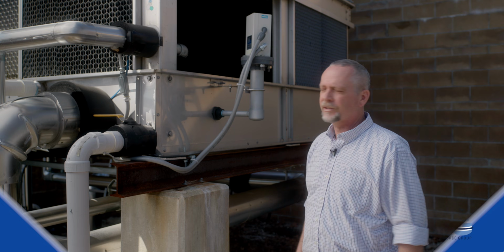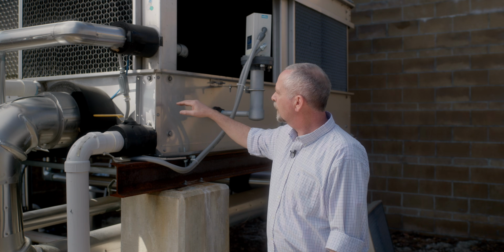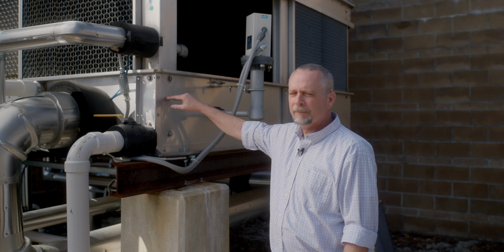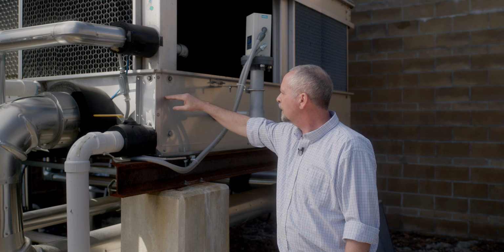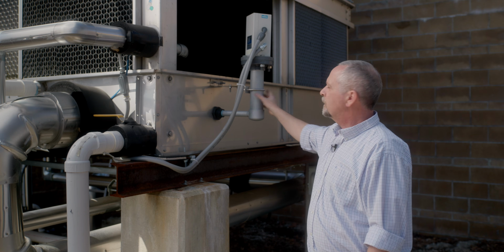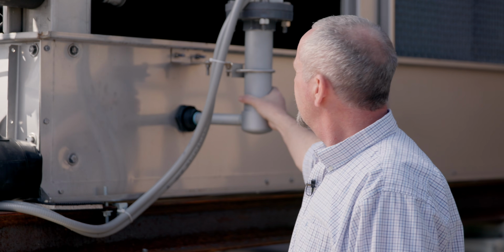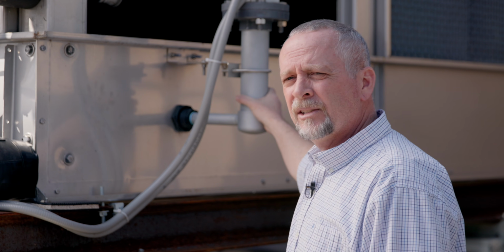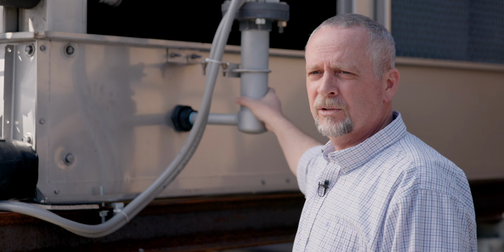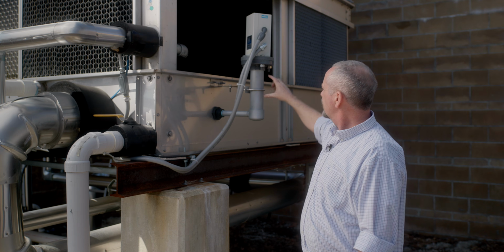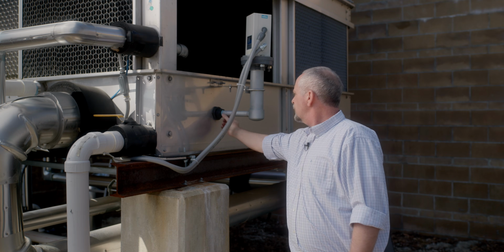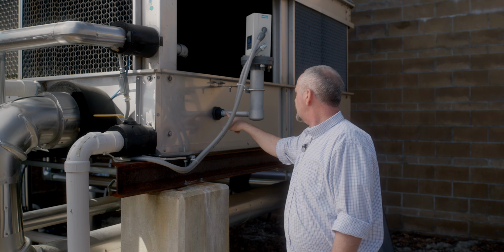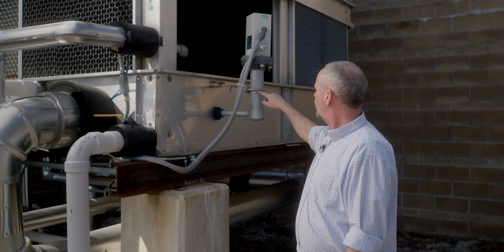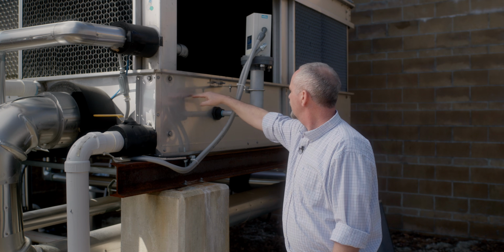Let's move on to how do we control the water level in the cooling tower. We know we need the water level to be right below the overflow pipe that we talked about earlier, roughly somewhere in here. And we control it with this device. This particular one is a Warwick brand, and it's an electronic water level controller. So basically, in a nutshell, inside this pipe, you can see this one coming out here. So there's my tower water running through here, and the water inside this pipe is right at the top level of the tower.